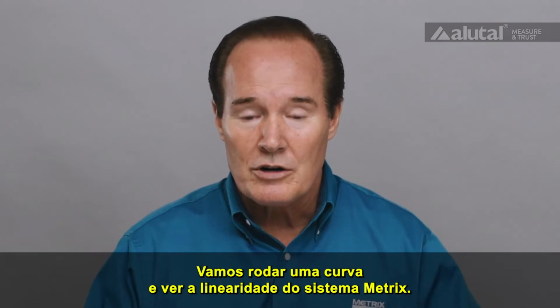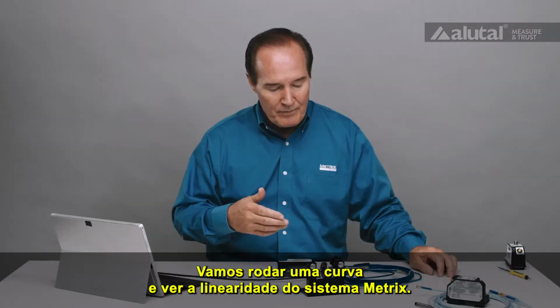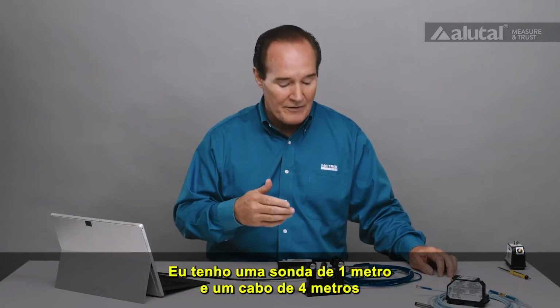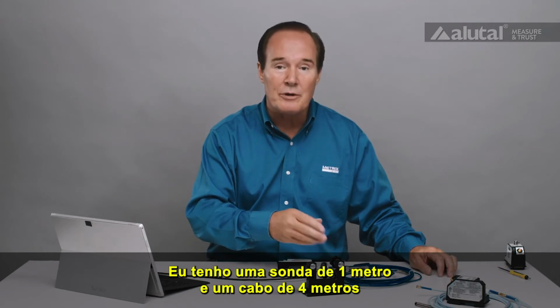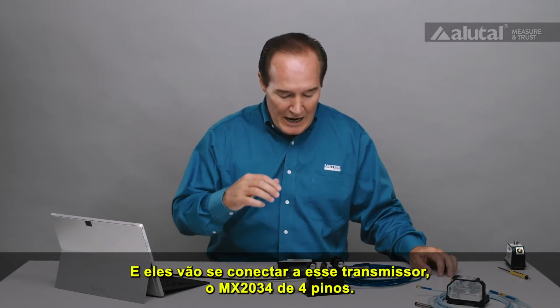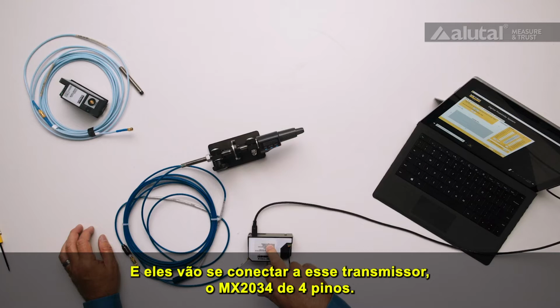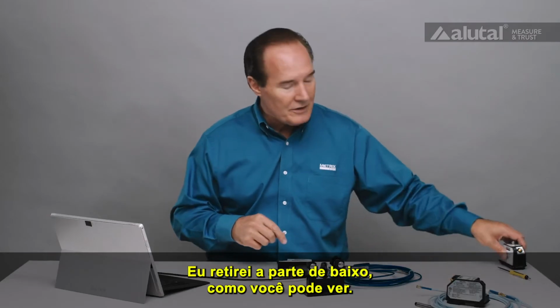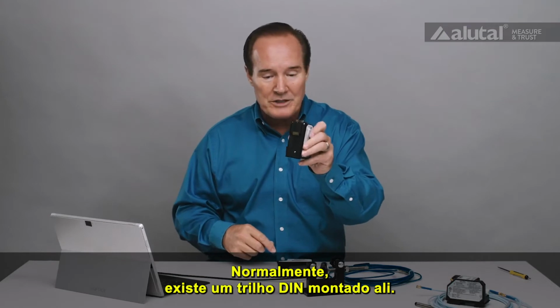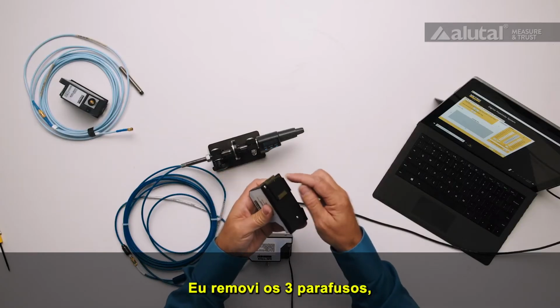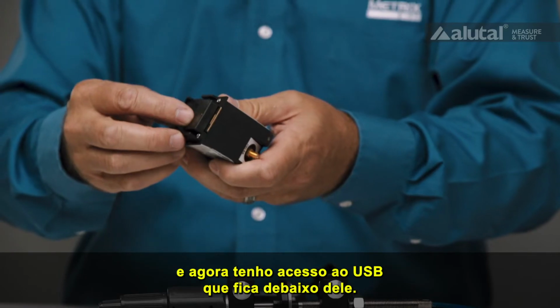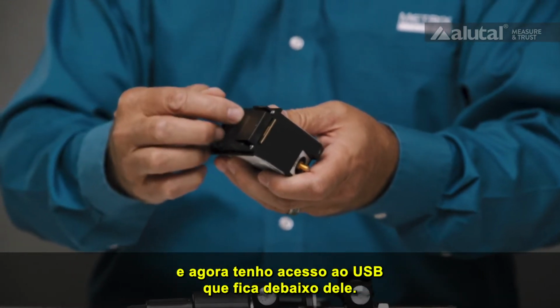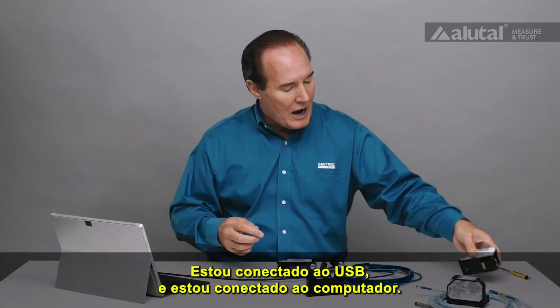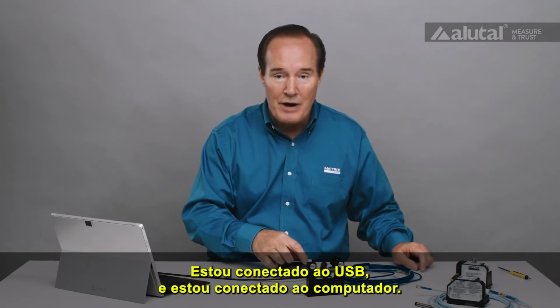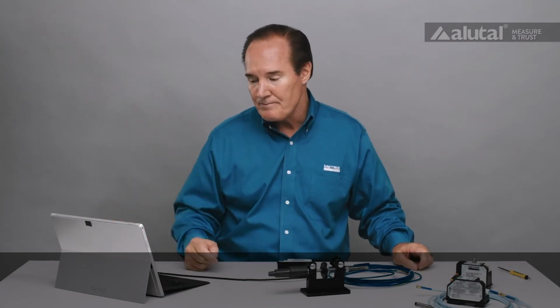Let's run a curve and let's see how linear the Metrix system is. I have a 1 meter probe and a 4 meter cable for a 5 meter system, and that's going into this transmitter, the MX2034 4-pin transmitter. Now I have the bottom taken off. You can see normally we have a DIN rail mounting on it. I took off these 3 screws, and that gives us access to the USB that's underneath it. So I'm tapped into that USB right now, and I'm connected to my computer.